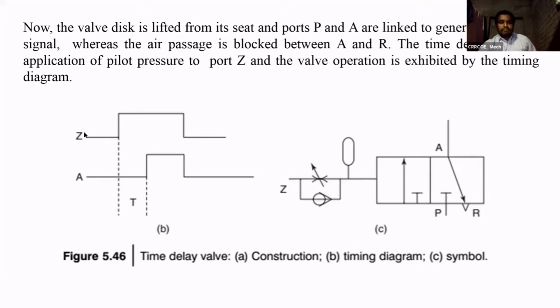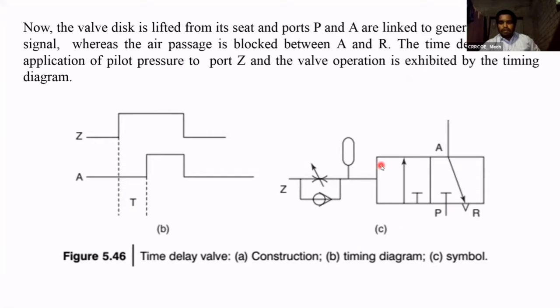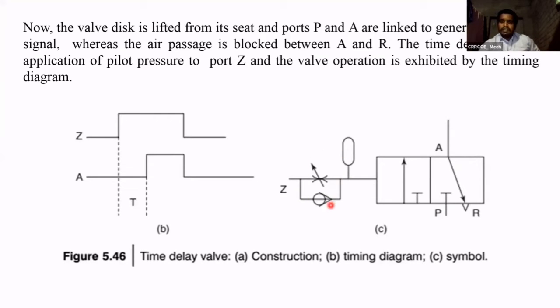This is called the time delay valve. The time delay diagram shows the pilot air and outlet port — there is a time delay between them. Based on this time delay, the valve is open or closed. We are setting that time. This is the symbol for the time delay valve. Z means the port for the pilot air. The pilot air operates the spool of the valve — it is operated by air, not manually. This circuit indicates the time delay circuit. This is the actual direction control valve, and this valve is controlled with the help of air from port Z, controlled by a time delay screw.